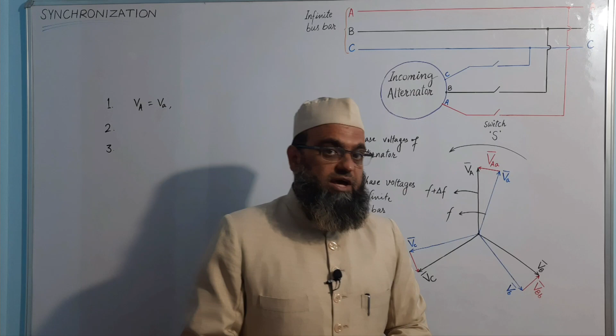And if this switch S is closed, then there will be no problem in the phase where the two voltages are coinciding, but the 120 degree phase displacement among the two sets of phasors of the other two phases will create again the same problem of point number 1. That is, it will cause large currents to flow in the two phases, which may damage the machine. That's why we have to take care of the phase sequences also under third condition discussed so far. Fine.